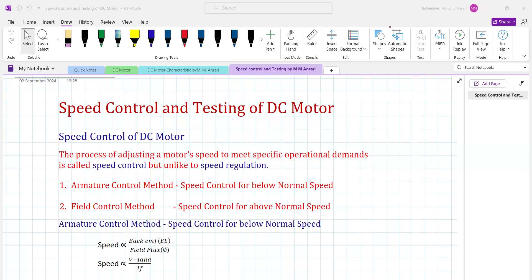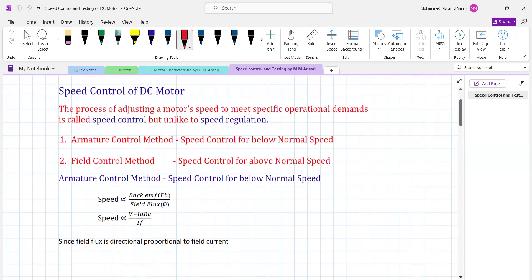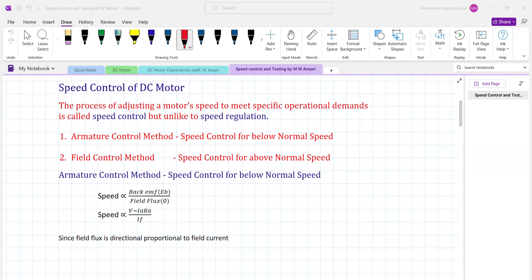There are two methods. One is the armature control method, used for speed control below normal value. For example, if the rated speed is 1500 RPM and we want 1400 or 1315 RPM, we use the armature control method. The field control method is used for speed control above normal value — for example, 1600 or 1650 RPM, which is greater than the normal value.